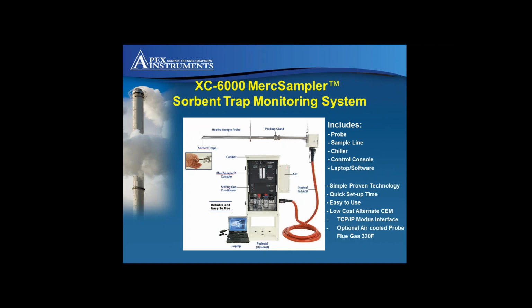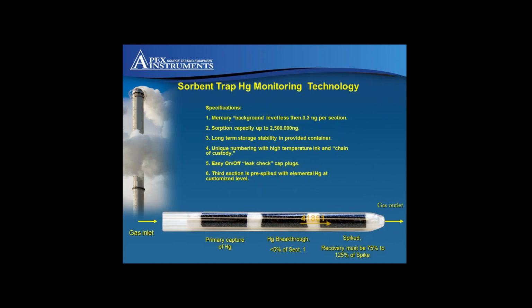A typical picture of the system hardware, although there is great flexibility in the equipment packaging to suit the process conditions and the test location, which I'll just touch on a little later. The test is always by paired sample trap collection. Sorbent traps conform to PS12B sampling and analysis specifications. High concentration of iodine deposited on acid washed activated carbon ensures extreme mercury capturing capacities without breakthrough for extended test periods in wet or dry stack emissions from coal-fired power plants.